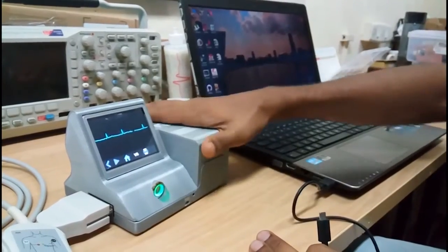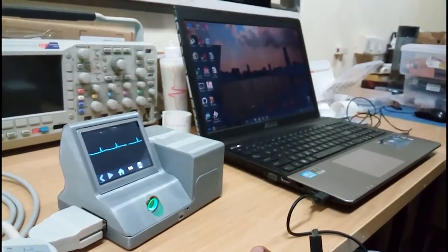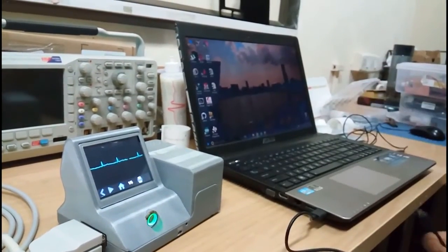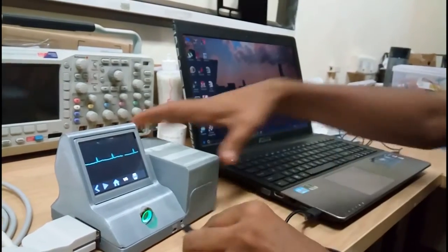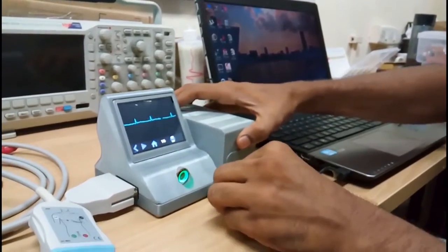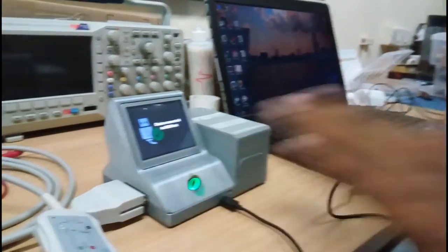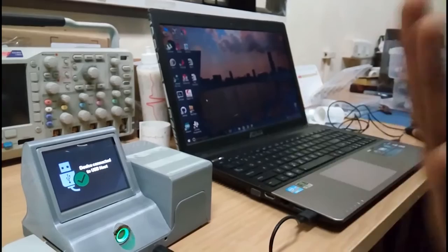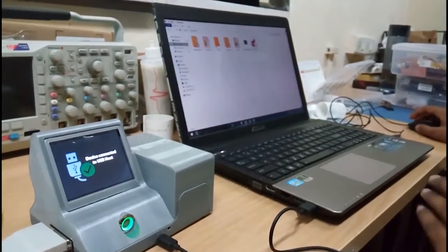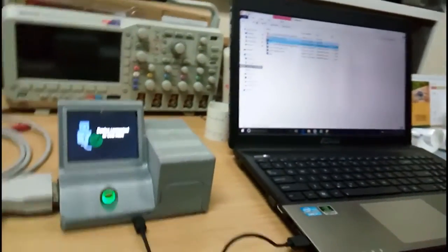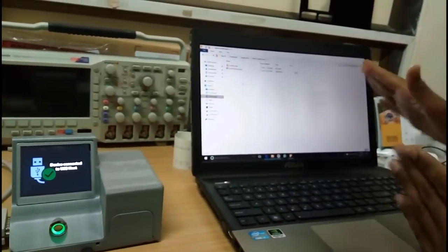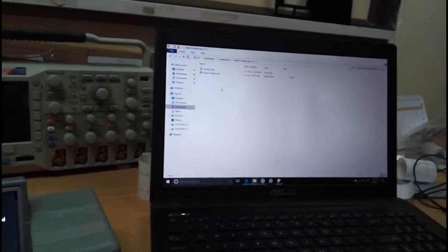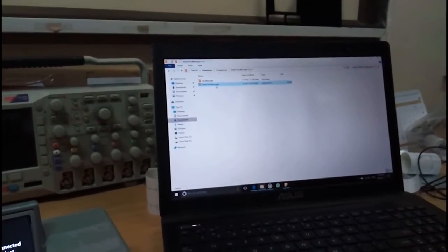We can also connect the device onto the computer and send all the 12 waveforms onto the computer to perform an automated diagnosis. Now, data is sent over a USB cable. The USB inside the device has been set in communication device class mode. So basically, it appears as a serial port. And as of now, our computer software is not ready, as I mentioned at the start of the video. So I'll just be showing it to you on this application called Serial Oscilloscope.